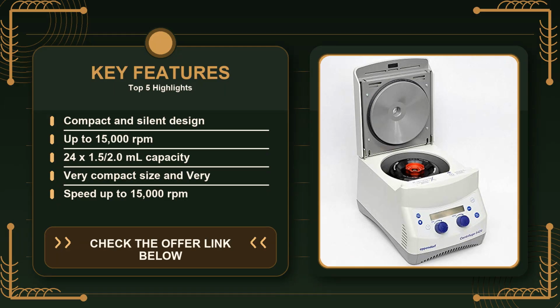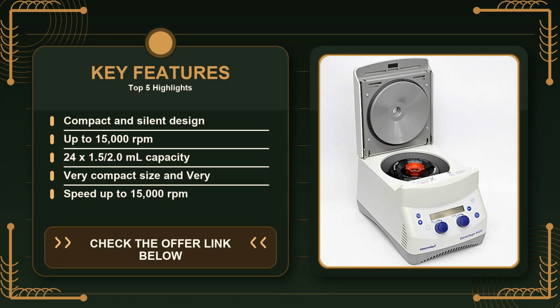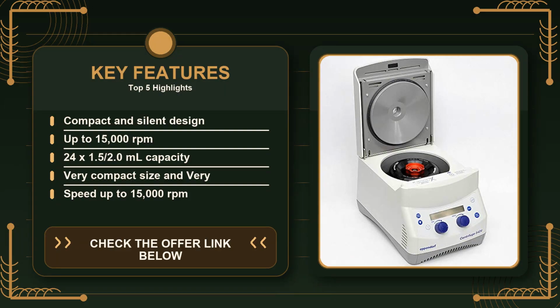On the flip side, there are clear situations where this model isn't the right choice. If your protocols require high-throughput spinning of 96 well plates, or you regularly need to process large volume tubes, say 5 milliliters or more, you'll quickly outgrow the 24-tube rotor. Likewise, if you are looking for an ultracentrifuge capable of 50,000 RPM or higher for sub-nanogram DNA work, the 5424 simply won't meet those demands.